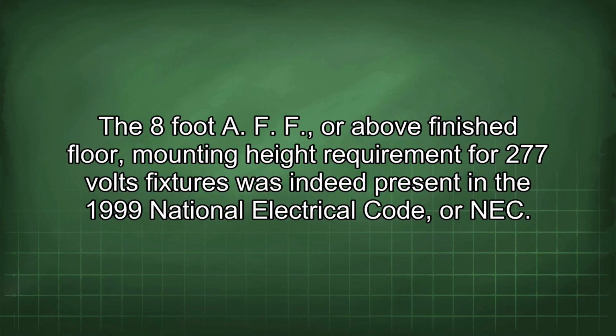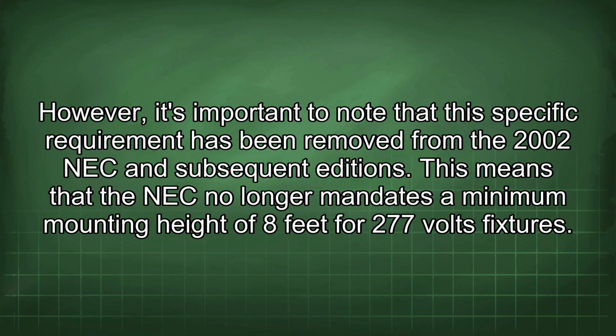The 8-foot A.F.F., or above finished floor, mounting height requirement for 277 volt fixtures was indeed present in the 1999 National Electrical Code, or NEC. However, it's important to note that this specific requirement was removed from the 2002 NEC and subsequent editions. This means that the NEC no longer mandates a minimum mounting height of 8 feet for 277 volt fixtures.